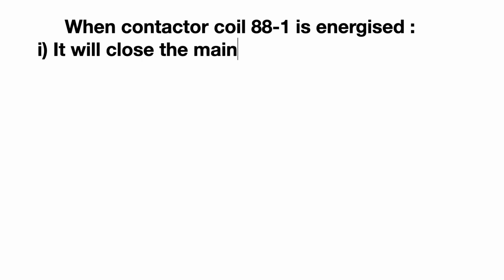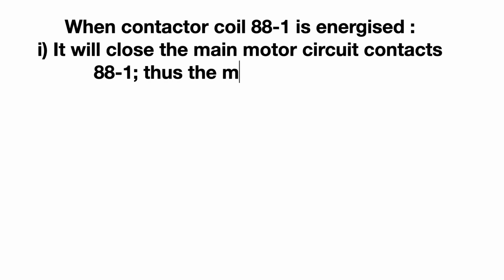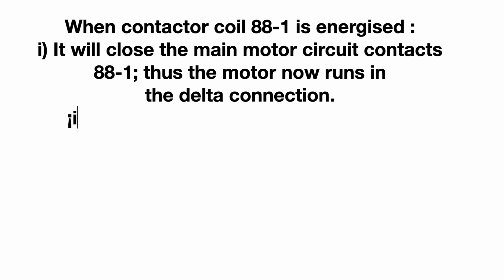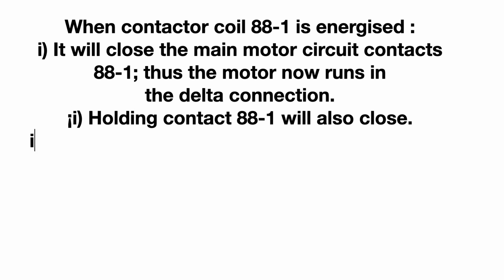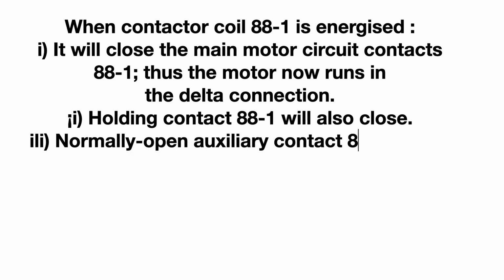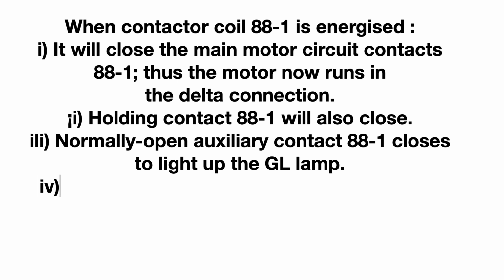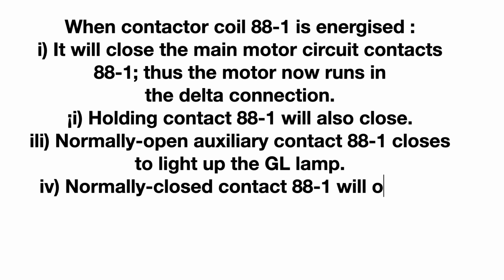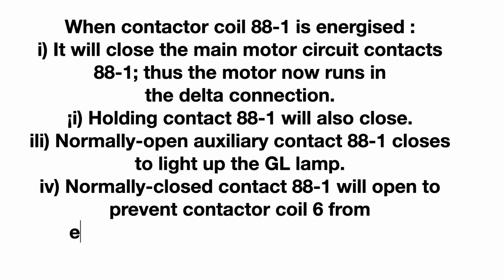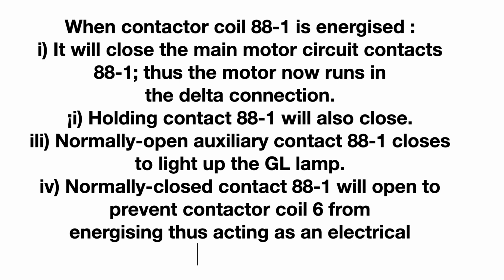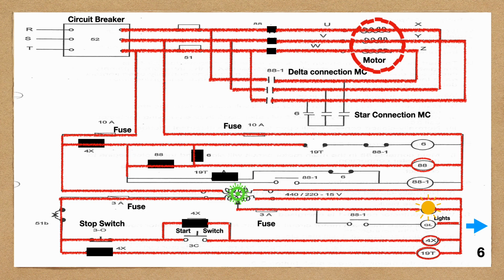When contactor coil 88-1 is energized, it will close the main motor circuit contacts 88-1, thus the motor now runs in the delta connection. Holding contact 88-1 will also close. Normally open auxiliary contact 88-1 closes to light up the green lamp. Normally closed contact 88-1 will open to prevent contactor coil 6 from energizing, thus acting as an electrical interlock. Motor green light turned on. Motor now running in delta connection.